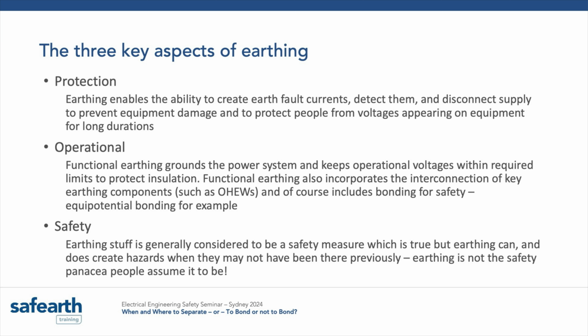The number two priority for earthing is operational, because you want to ground your transformer and your power system. You need to keep the voltages within a specified limit so you don't create over voltages on your insulation and break the system. Then third is safety, because we all think earthing's about safety, right?